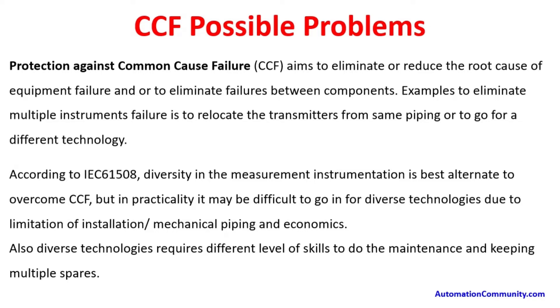IEC standards recommend going for diversification — that means two different technologies for the same type of measurement. It would be ideal, but in practice, plant space may be limited and putting multiple instruments on the same piping can be a challenge for installation, maintenance, and cost. Additionally, diverse technologies require different levels of skills for maintenance and people may not be skilled enough to work on both types of instruments.